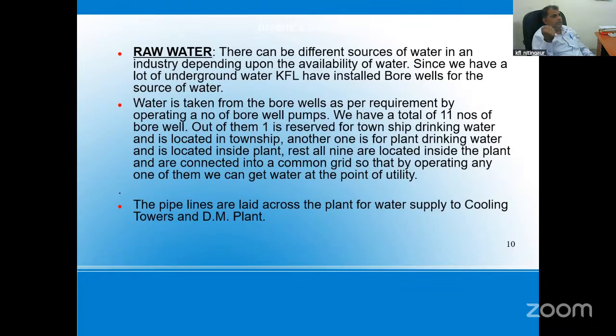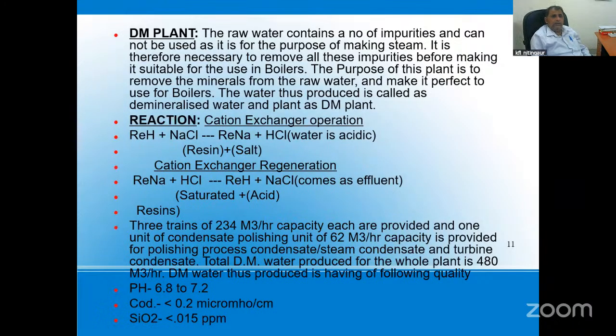If we use raw water as boiler feed, then the minerals available in the raw water deposit on the tube surface. It means scaling forms. This scaling will reduce the efficiency. Why? Because heat transfer will not be proper. If heat transfer is not proper, then a huge amount of gas is required. So the efficiency of the boiler is automatically reduced. To make the available raw water usable for steam generation, the utility plant also has a DM plant. DM plant means demineralized water plant.